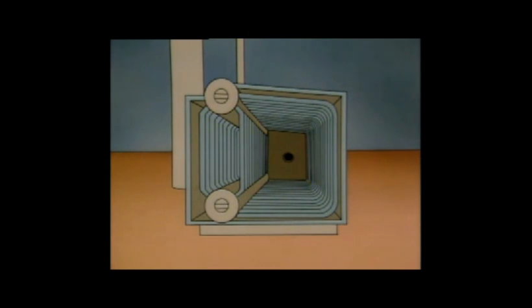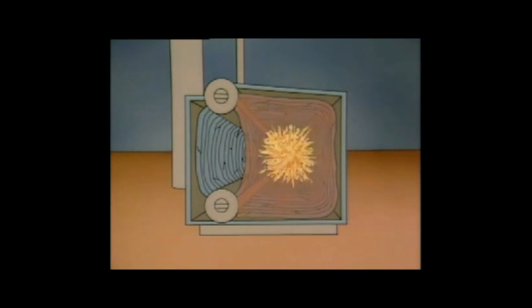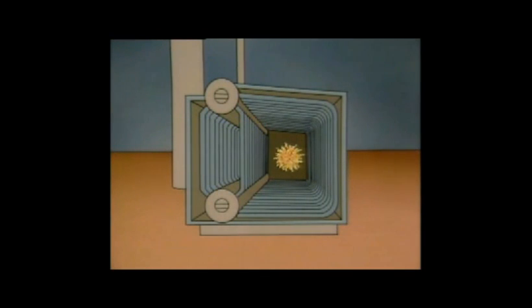The last problem we'll look at is improper warm-up, which may occur if the boiler isn't started up correctly. Water tubes and other metal parts expand when they're heated. If the boiler hasn't been operated for a while and is then rapidly heated, its metal parts may expand at different rates, causing some parts to bend or break. To protect the boiler, heat must be applied gradually to ensure that all the metal components expand at the same rate.